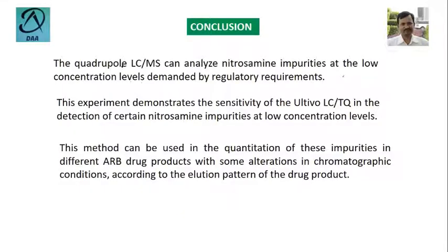So conclusion: this triple quadrupole LC-MS can analyze nitrosamine impurities at the low concentration level demanded by the regulatory requirements. That means regulatory requirements demand detection at very low concentration levels, and this experiment meets the need for the determination of all 12 types of nitrosamine compounds.